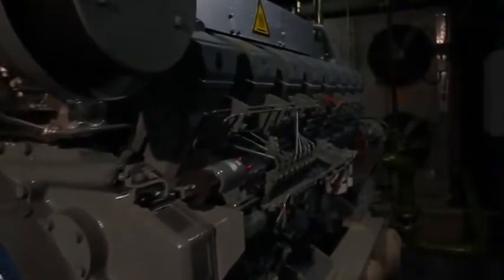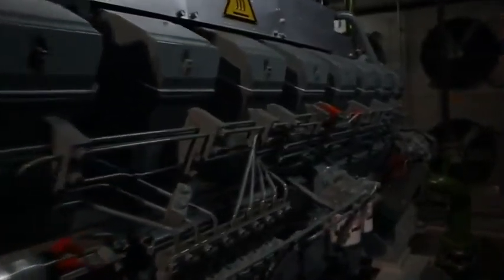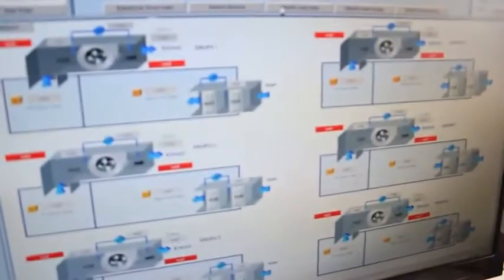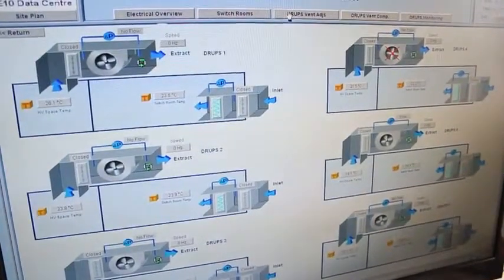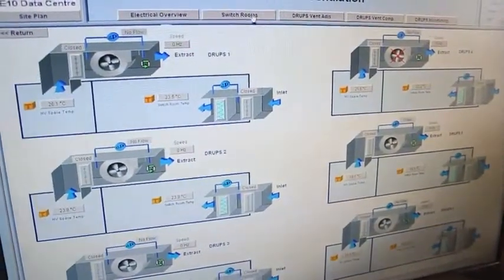We have diesel rotary UPS systems which smooth out any electrical disturbances and provide protection in the event of a long-term mains failure. One of the reasons we chose diesel rotary UPS was to eliminate the very large battery banks that are associated with static UPS systems. These battery banks require periodic replacement and have a significant environmental impact. The DRUPS systems are efficient and have lower losses than typical static UPS systems. They also take up less space, which enables us to maximise the amount of data hall space we could provide.